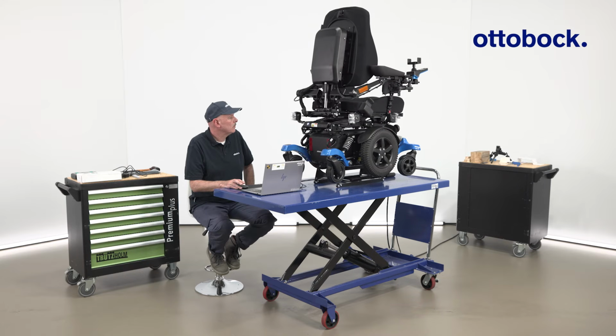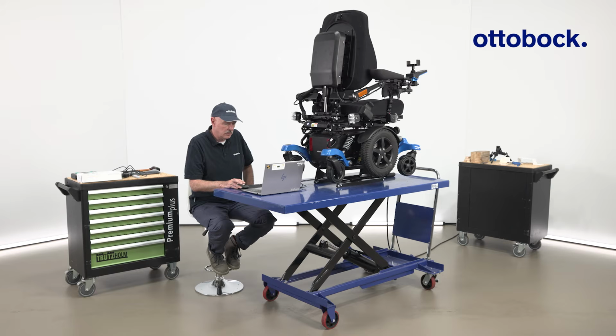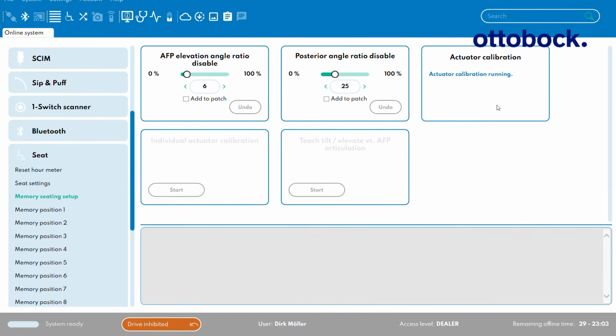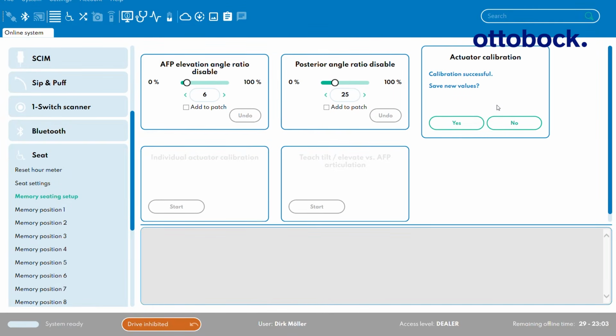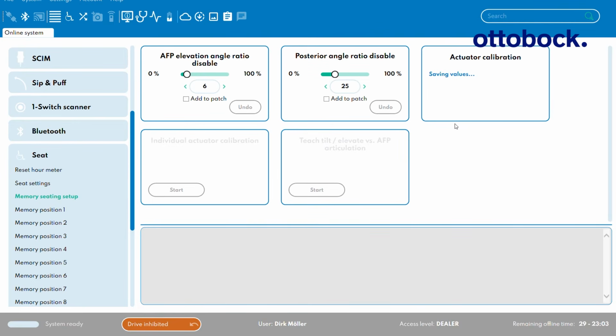The wheelchair now automatically runs the calibration for all actuators installed in the system. Once the process has been successfully completed, confirm the data storage in the connected system. All values are then saved according to the calibration results.